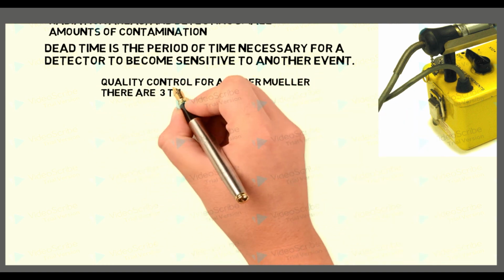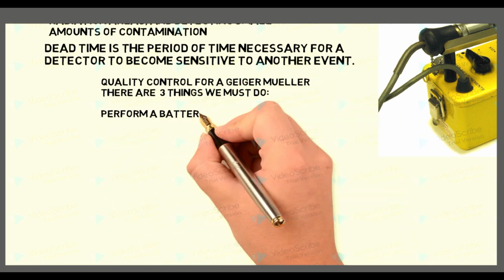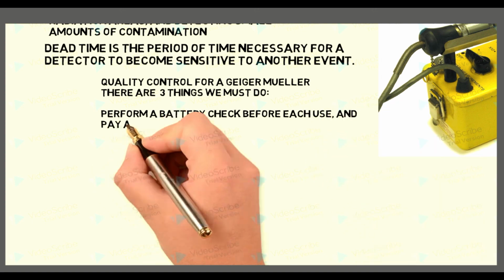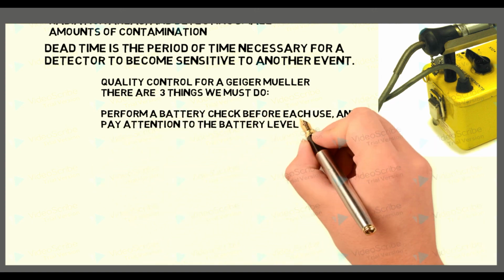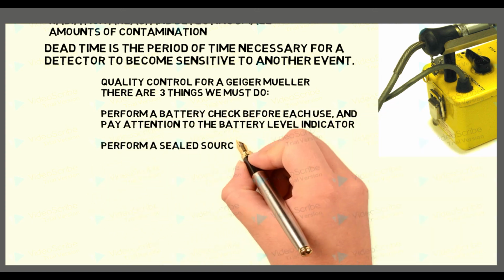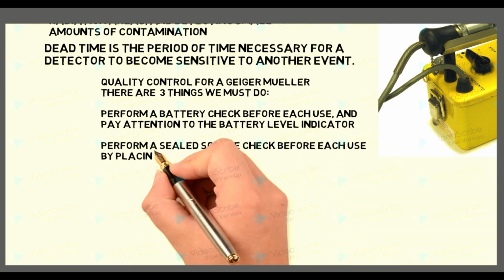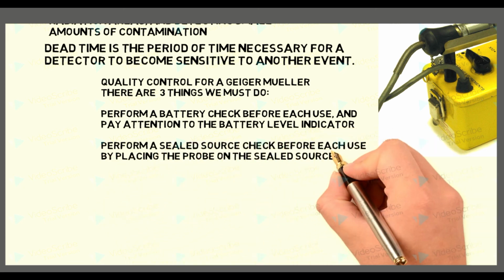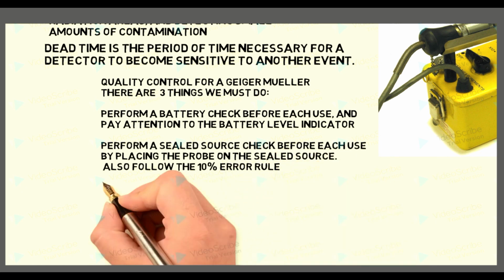Quality control for a Geiger-Müller. There are 3 things that we must do. Perform a battery check before each use and pay attention to the battery level indicator. Perform a sealed source check before each use by placing the probe on the sealed source. Also follow the 10% error rule.